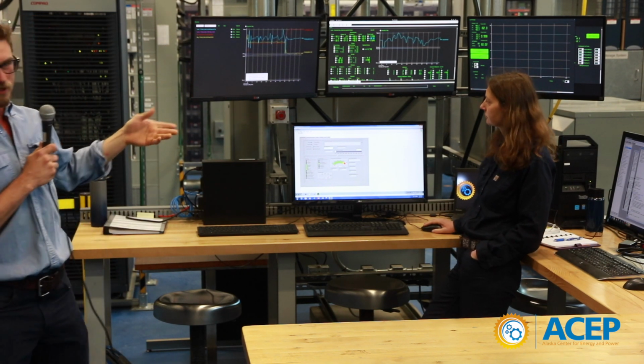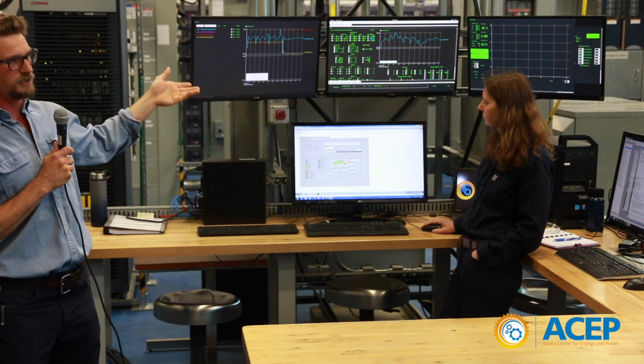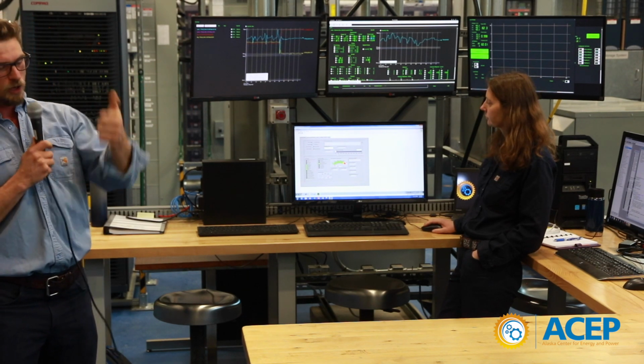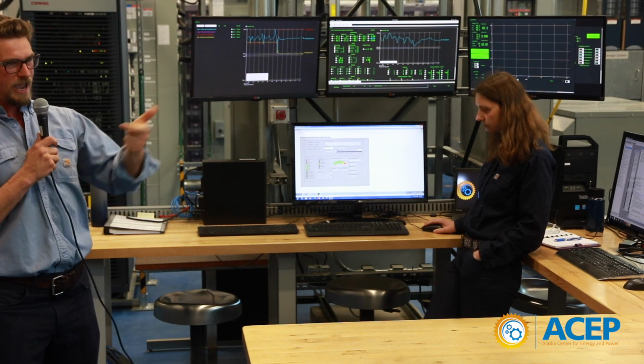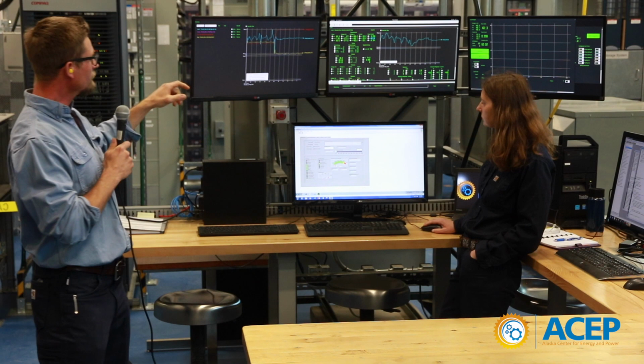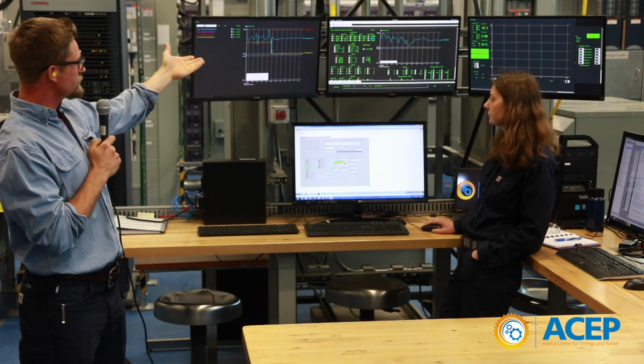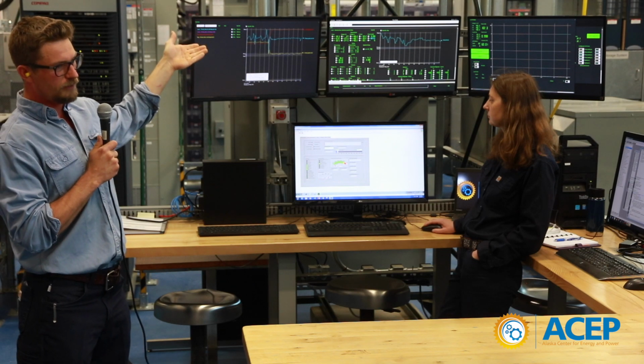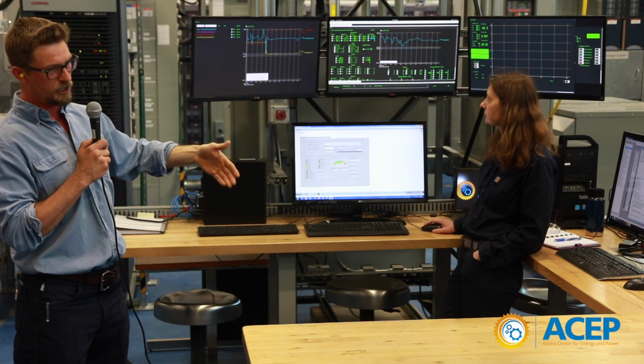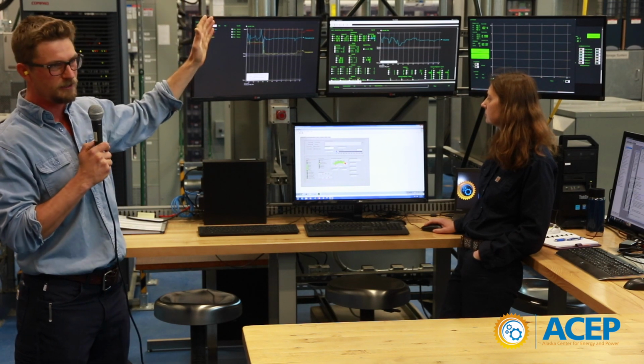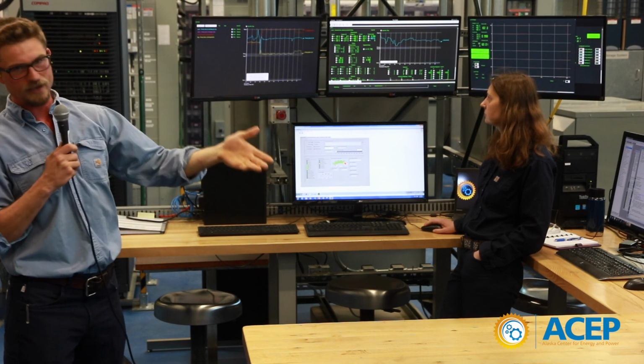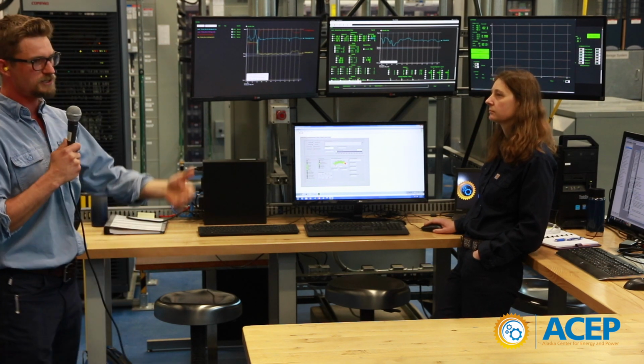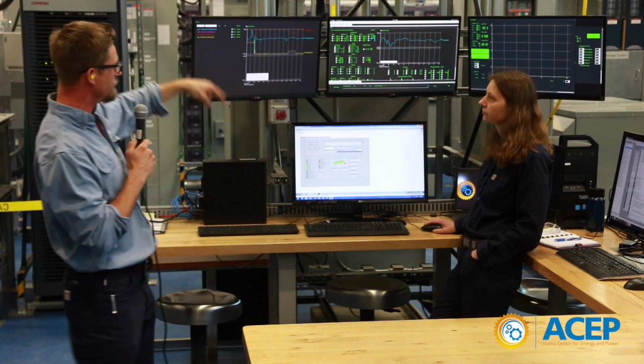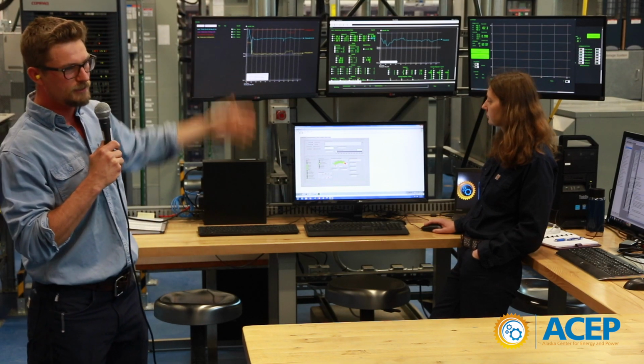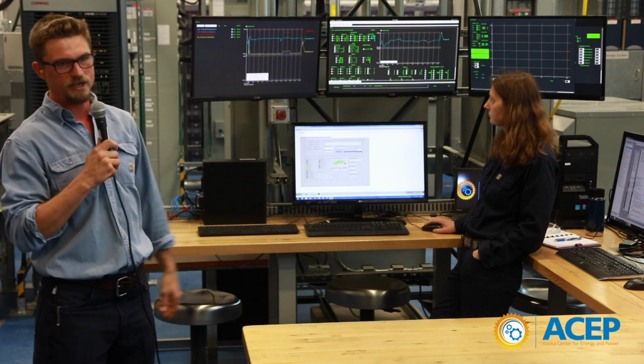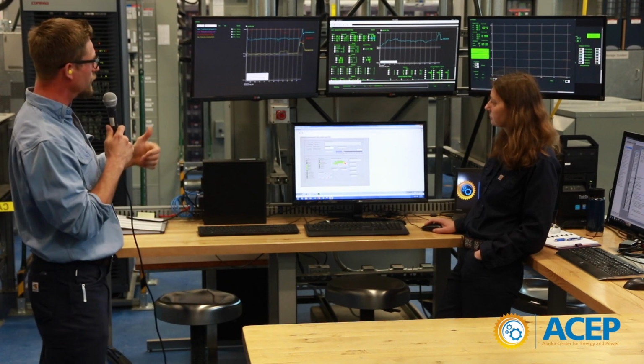But so as a customer, this is what you want. You don't want there to be a noticeable difference in your supply of electricity. You don't want to pay too much money for fuel, right? And you want there to be electricity. And this is a service that the generator provides. When there's a drop and that wind power goes down to 0, the generator just picks up that load like nothing happened, and you still have electricity. You pay for that by buying fuel, right? So there's a cost to that. That's the service it provides, and it does a great job. We can ramp this wind power up and down as much as you want, and the generator is just going to make up the difference. So it's a great tool.